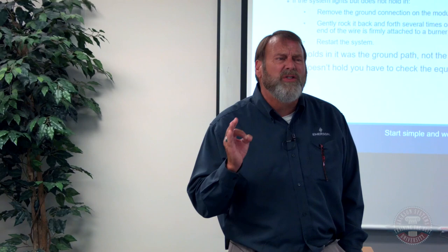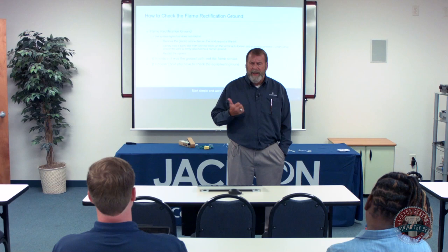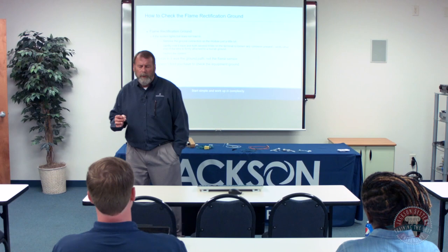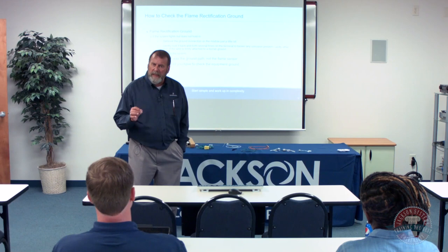And here's the kicker. What are the byproducts of combustion? Hydrogen, oxygen, carbon, and a whole bunch of other chemicals I can't spell. They create films of corrosion on your quarter-inch spade terminals or your ring terminals on the burner manifold that will result in you not having a good, firm ground bonding plane. And that's the key to keep in mind.